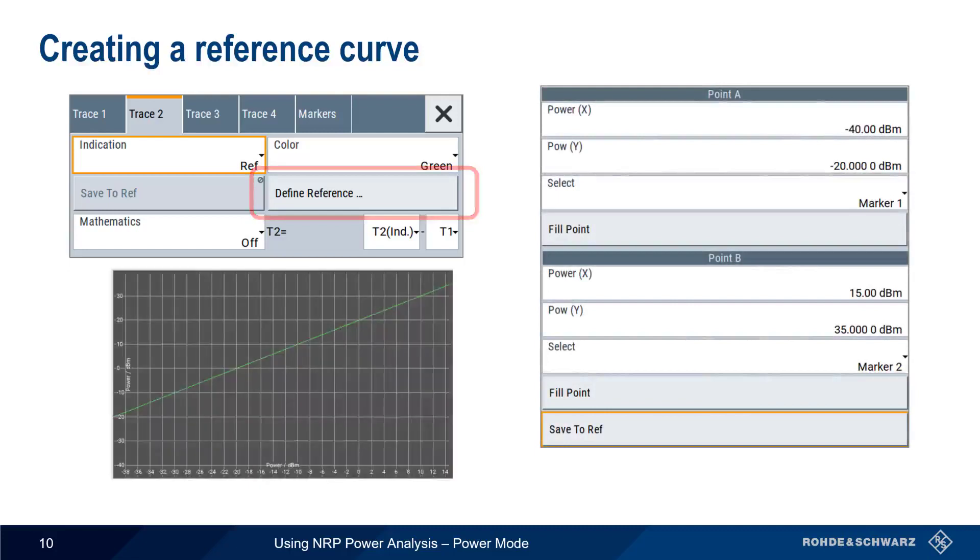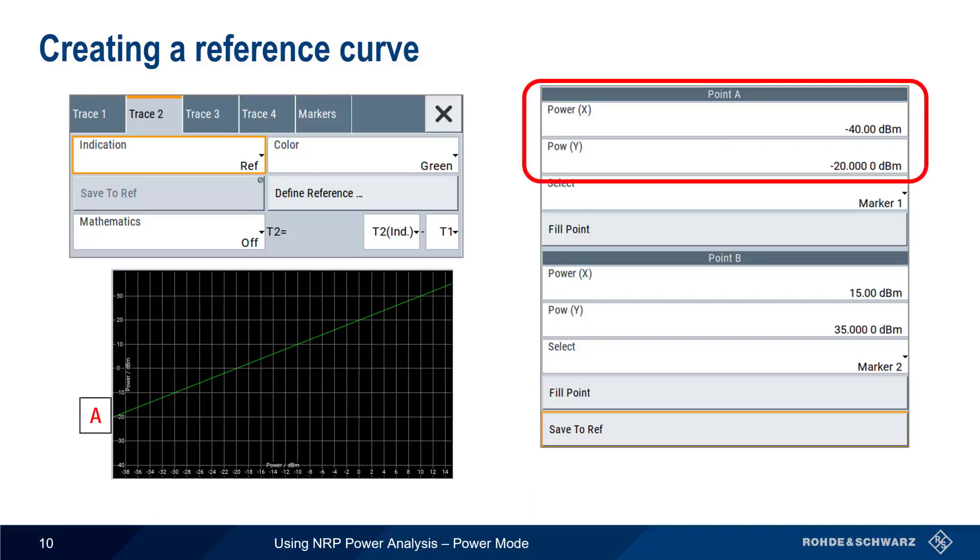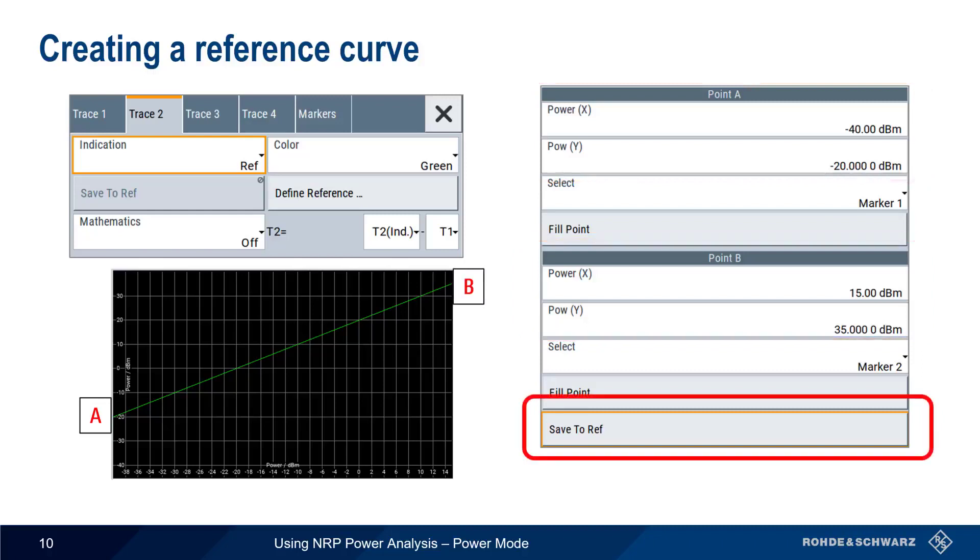Trace 1 is our measured amplifier output, and we'll define trace 2 as our reference curve. Using defined reference, we'll create a constant gain line of 20 dB, by choosing a starting point of minus 40, minus 20, and an endpoint of plus 15, plus 35. We save this curve to ref, and then set trace 2 indication to ref.